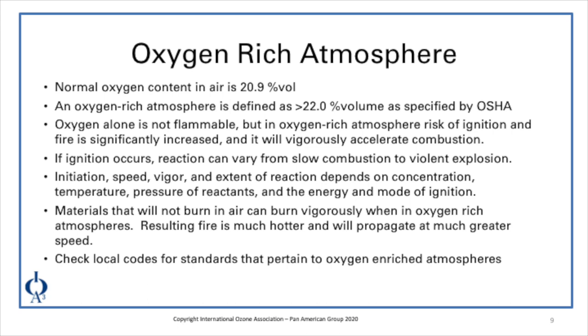Looking at an oxygen-rich atmosphere, the normal oxygen content in air is 20.9% by volume. OSHA defines an oxygen-rich atmosphere as being something greater than 22% by volume. Oxygen itself is not flammable, but in an oxygen-rich atmosphere, risk of ignition and fire is significantly increased, and it will vigorously accelerate combustion. If ignition occurs, the reaction can vary from slow combustion to violent explosion. The initiation, speed, vigor, and extent of the reaction depends largely on concentration, temperature, pressure of reactants, and the energy and mode of ignition. Sometimes materials that will not burn in air can burn vigorously in oxygen-rich atmospheres, and the resulting fire is much hotter and will propagate at a much greater speed.